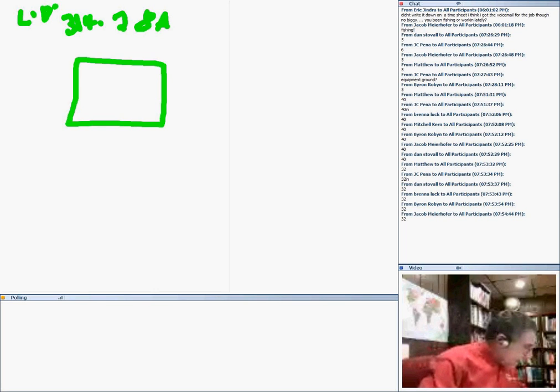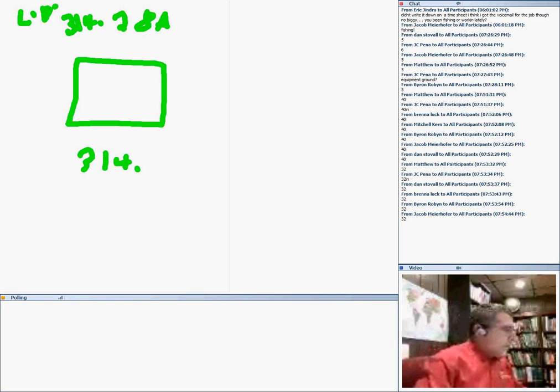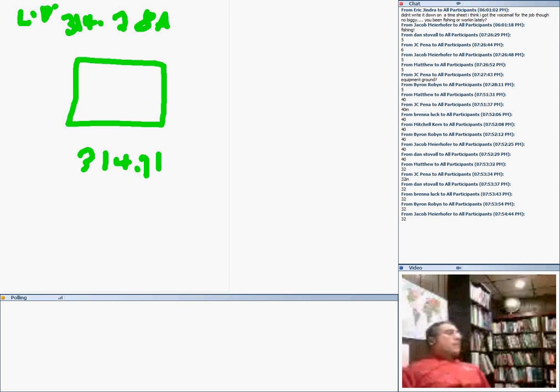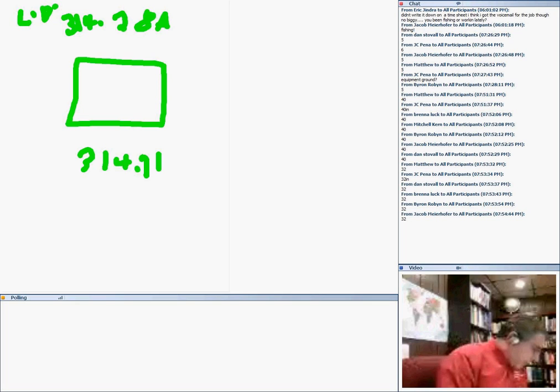High voltage, over 600, you need to go to exactly what we were just saying, guys. 314.71. If you have a handhole for high voltage, size it based on a pull box for high voltage. And if it's low voltage, then size it based on a pull box for low voltage. So, underground raceways and cable assemblies entering a handhole, they shall extend into the enclosure, but will not be required to be mechanically connected to the enclosure.